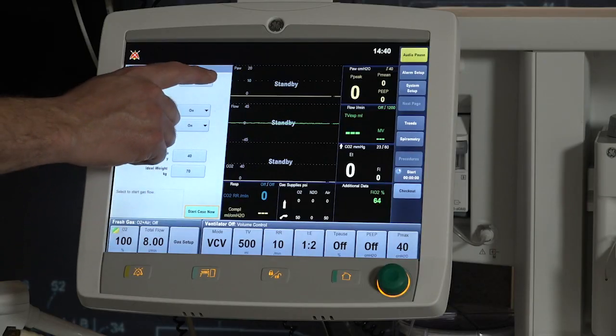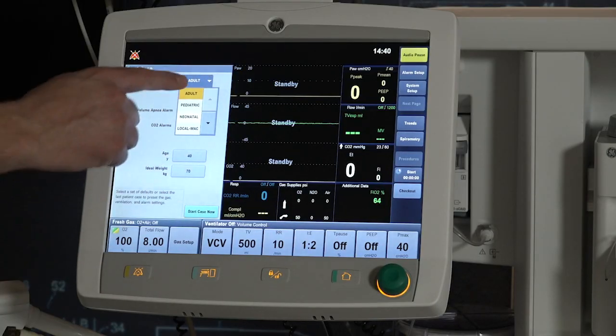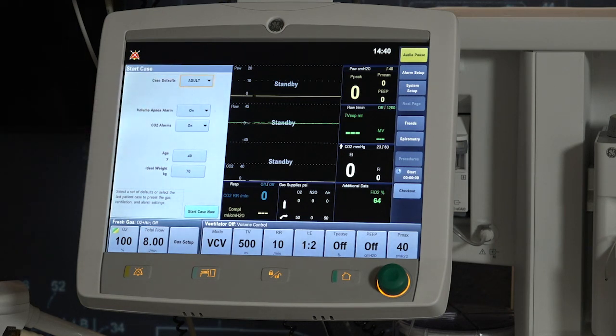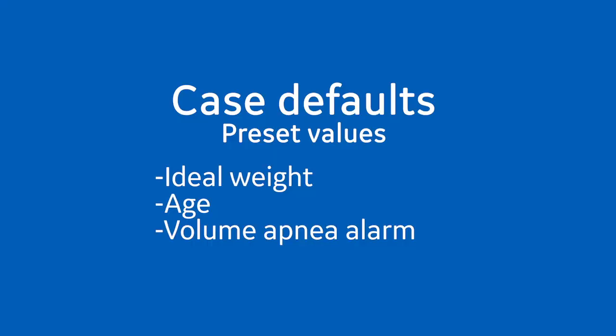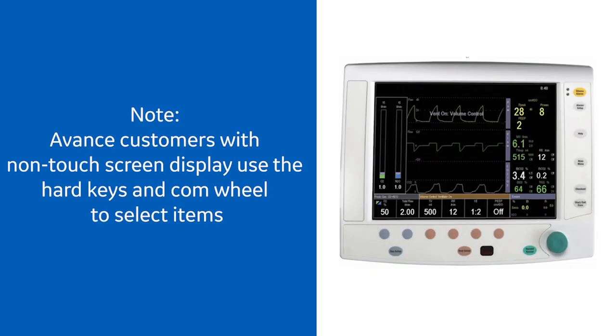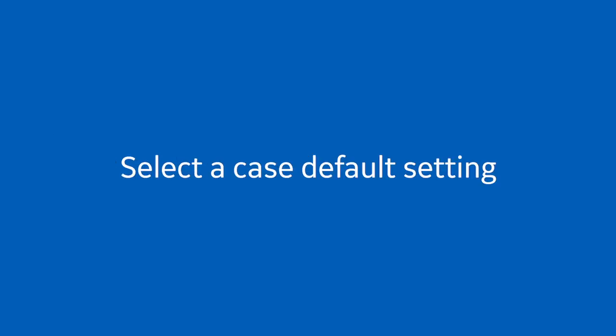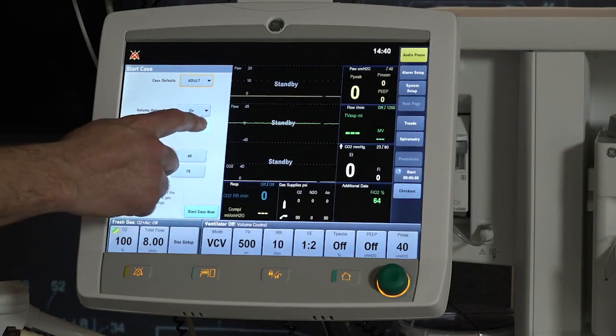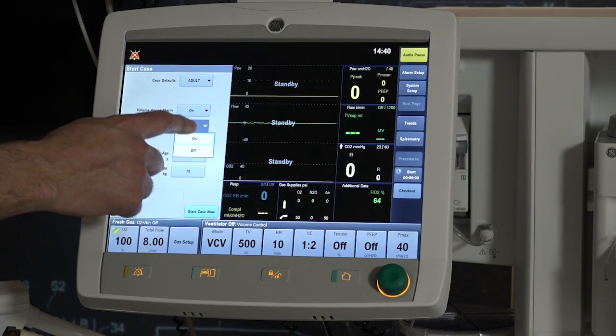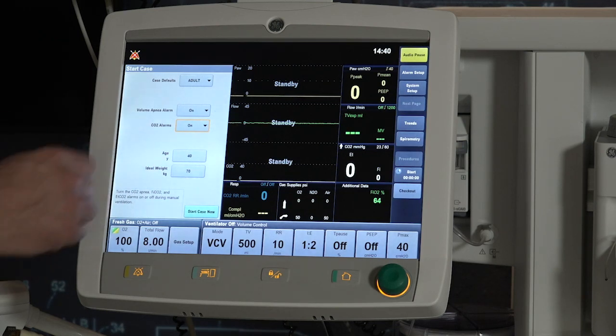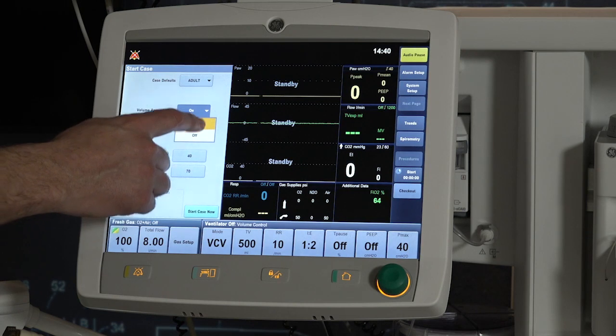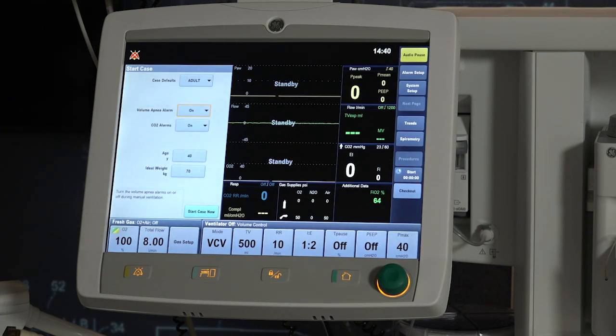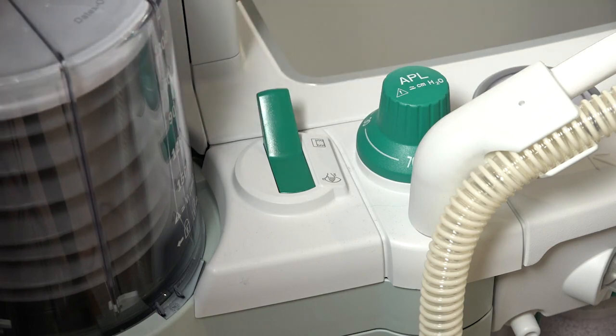A case can be started using default or custom settings. The case default selection shows the 4 default case types and the ability to use your last case setting. Each case type has a preset value for ideal weight, age, and volume apnea alarm. To select a case default, select a case type from the menu. The volume apnea and CO2 alarms can be left on or turned off. If the volume apnea and CO2 alarms are turned off, they will turn back on once the bag to vent switch is moved to ventilation.